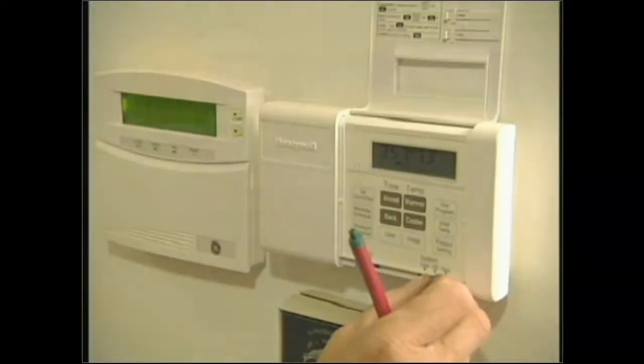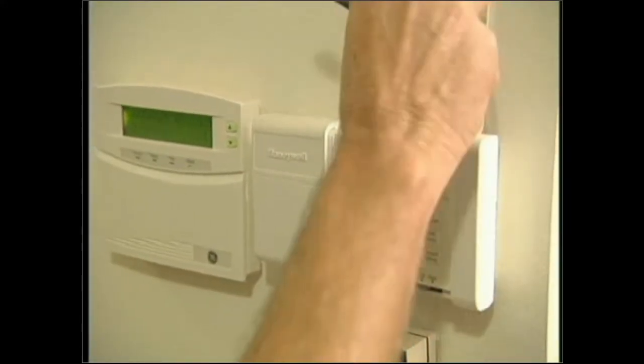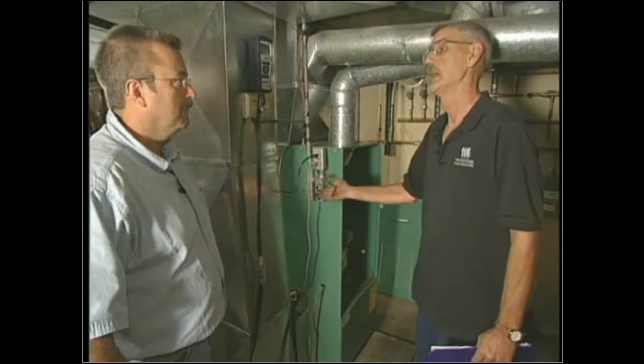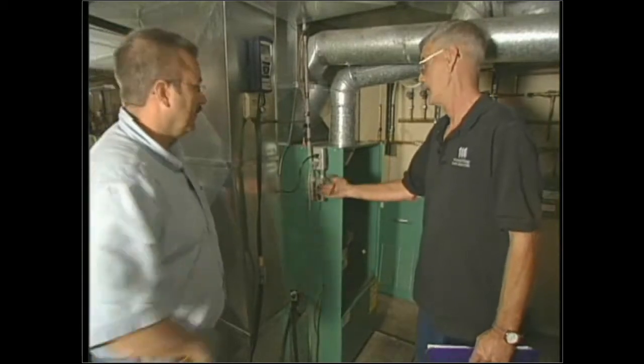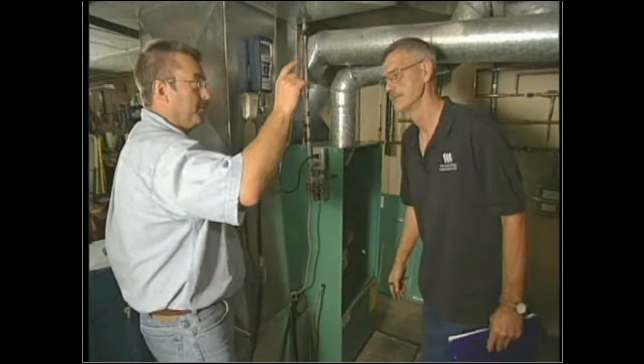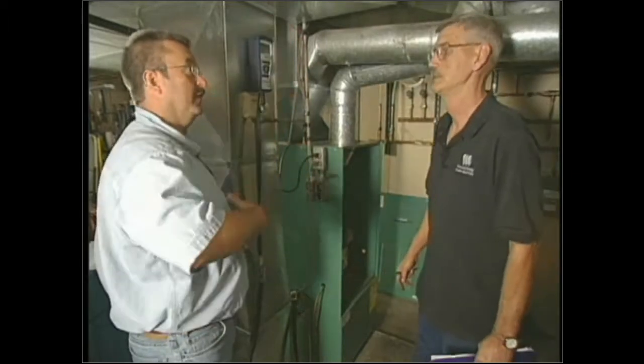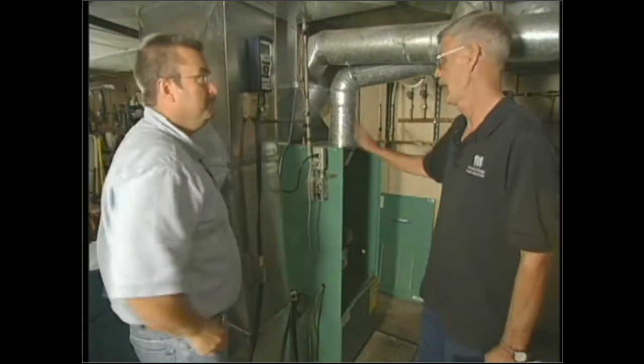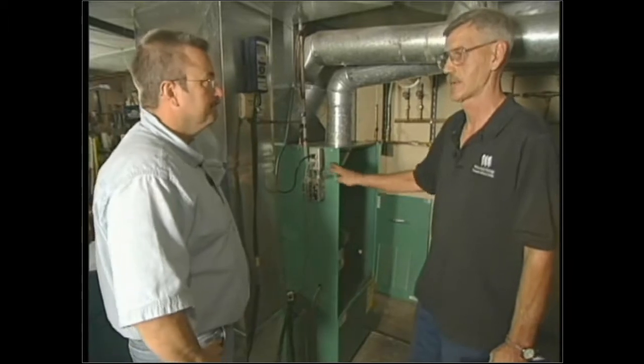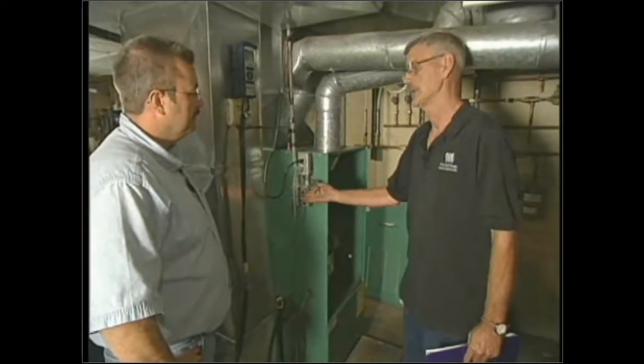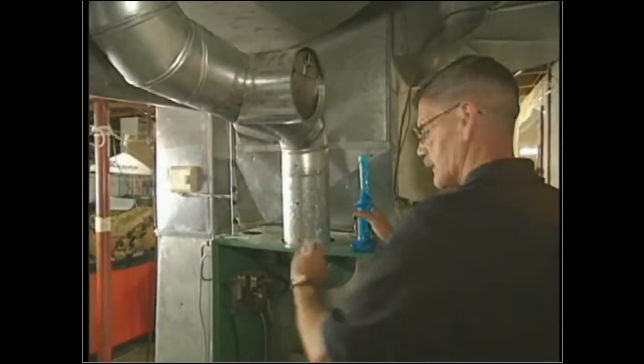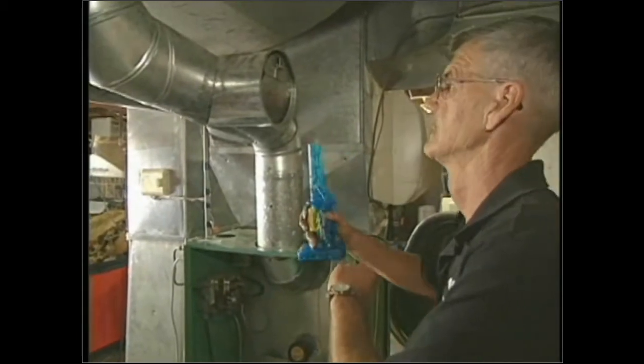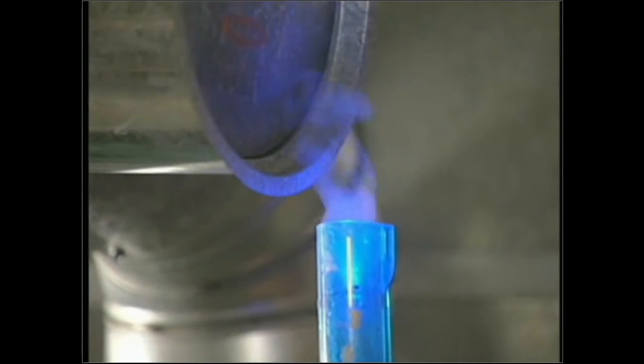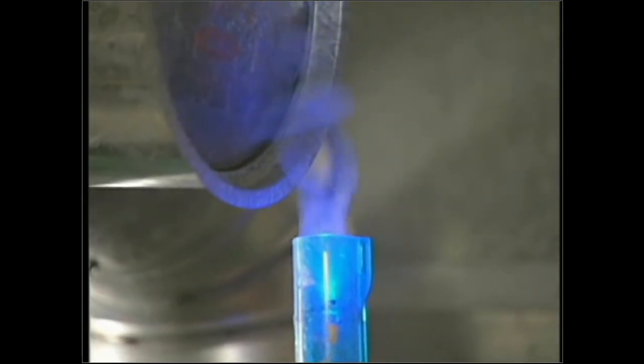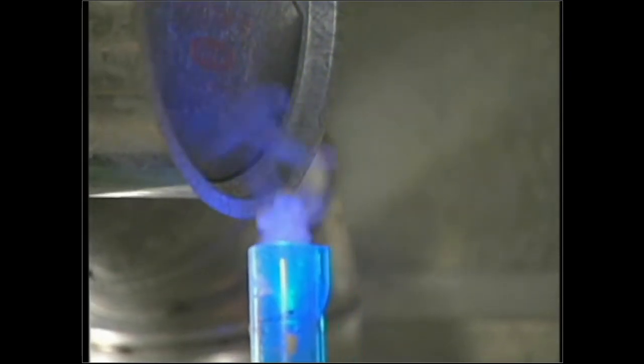So what that entails is I set the temperature at the thermostat, I come down here so I can control it with the switch. Okay, so you turn this off, go up to the thermostat, turn it to a nice high reading, so now I have control in close proximity where I want it. Then what I'll do is I'll turn this on, and I'll take my smoke generator, and I'll go back to the draft diverter, and just like we did on the 70s and 80s, I'll pass it up along the barometric control, and I will clock it after 1 minute. I can't have spillage after 1 minute.